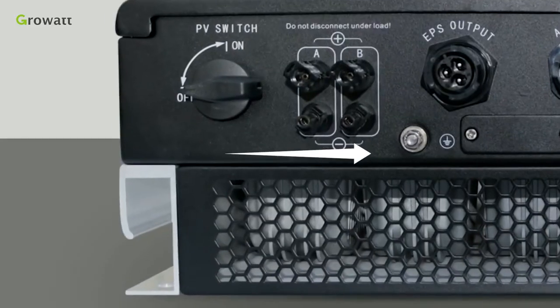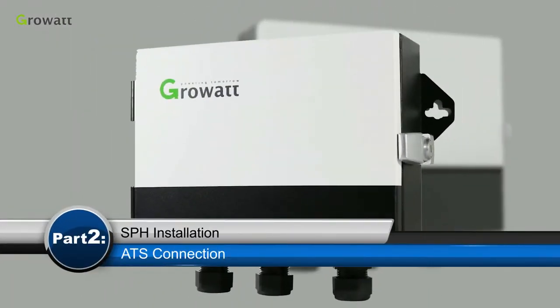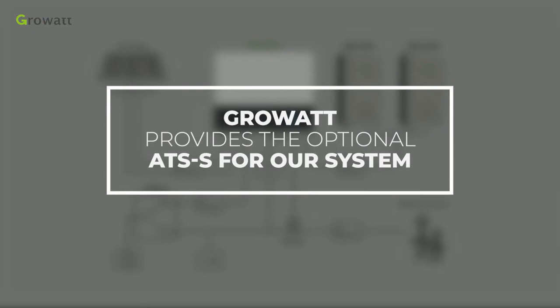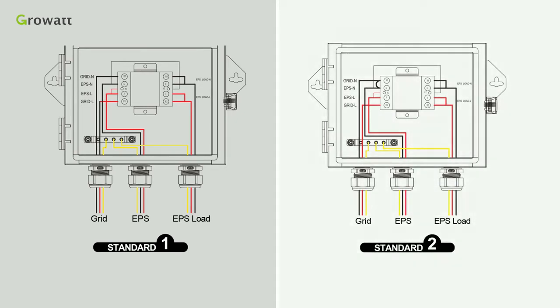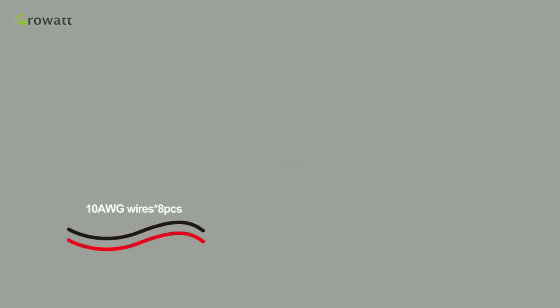The grounding connector is at the bottom of the SPH. If the customer requires the backup power function, Growatt provides an optional ATS for the system. We can follow the diagram to connect the ATS. Standard 1 is for general use, and Standard 2 is for markets like Australia where the neutral line cannot be switched. Wires are needed before installation.